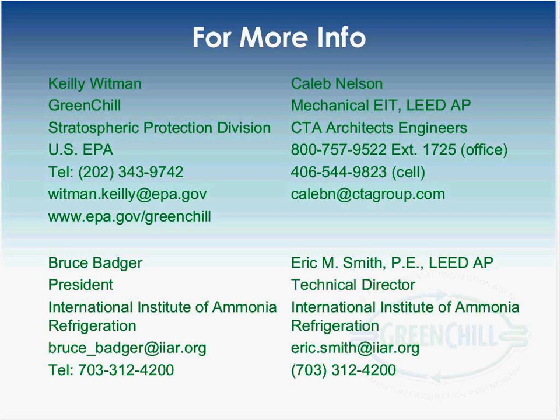Thanks much. The question concerns relief equipment - some jurisdictions require what's called a sparge line, which is a piping system below the pressure relief safety valve that exits the building, so the fire department can open the valve to dump ammonia into the atmosphere through a device with a fire hose connected to it. Have you done any research and/or findings on that type of system?